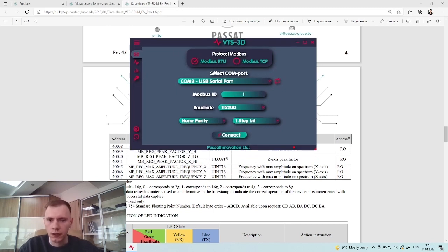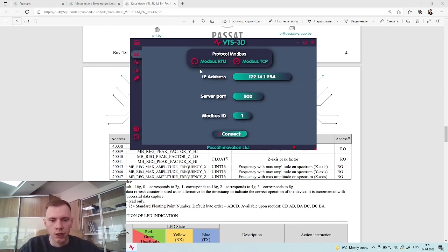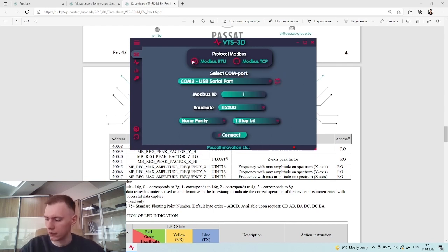Here we can see the connection page where you can choose the Modbus protocol. Our software supports two protocols: Modbus RTU and Modbus TCP. To connect via Modbus TCP, you need to set the IP address of your gateway, your port number, and the Modbus ID of the VTS 3D sensor. I will choose Modbus RTU because my sensor is connected via COM port, via USB converter.